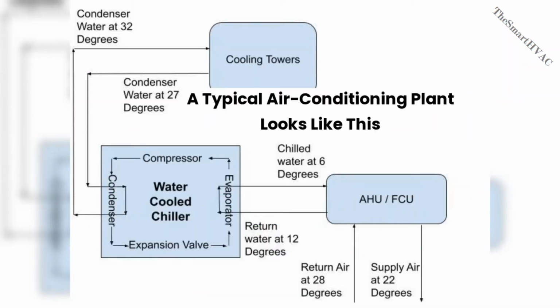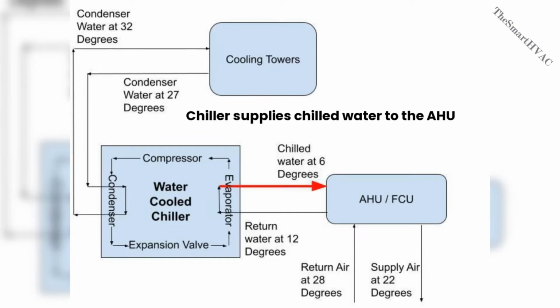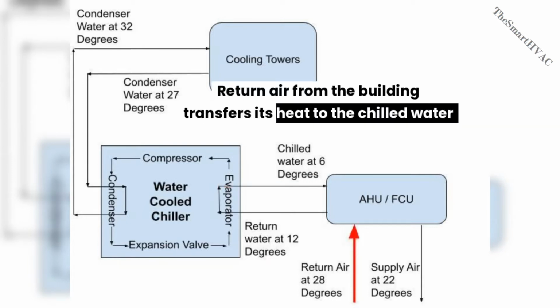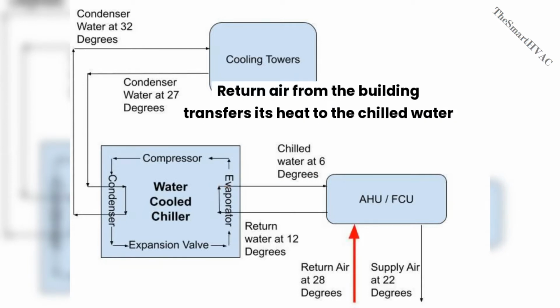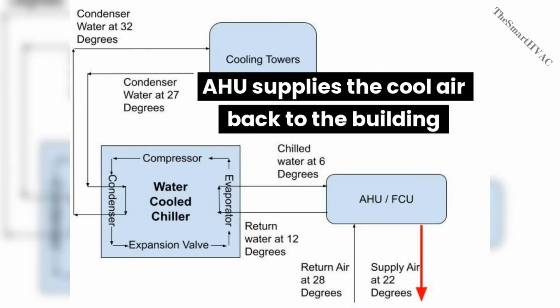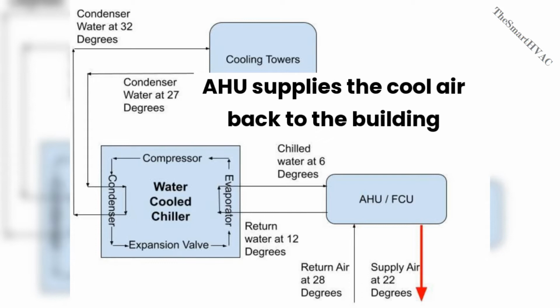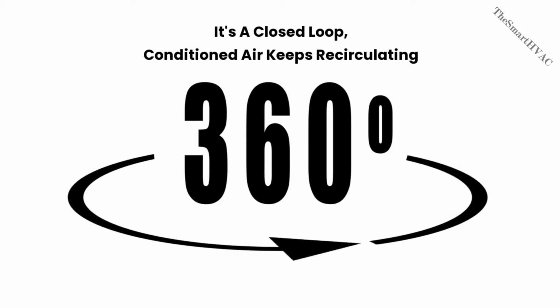Let's analyze this. A typical air conditioning plant looks like this. The chiller supplies chilled water to the AHU. Return air from the building transfers its heat to the chilled water, and the AHU supplies cool air back to the building. This is a closed loop wherein the conditioned air keeps recirculating across the building.